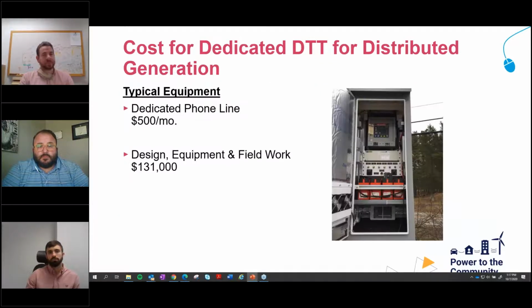Next slide. This is the installation we did — we did one traditional installation. This was the DTT box at the DER site. That box is 5 feet tall, 3 feet deep, 3 feet wide. A decent sized thing that went on a pole, and this ties into an electronic recloser that provides the tripping for the site. As you can see, quite a chunk of change to put this solution in, and the developers of the solar site have to pay for this, so it greatly increases their cost and reduces the feasibility of their site.